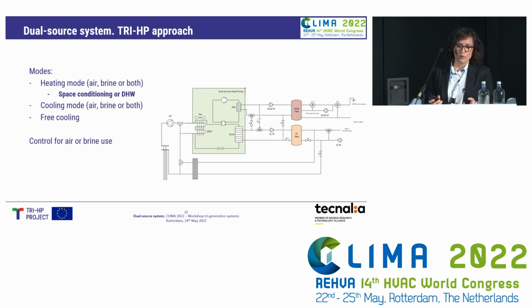Okay, this is an overview of the heat pump included in the building's thermal system. It can work in heating mode using air, the fan here, brine from the geothermal boreholes, or both at the same time, in order to provide space heating and domestic hot water. It's reversible, so it can also work in cooling mode, the same as in heating mode, with air, brine, or both at the same time. The system can also provide free cooling by exchanging heat directly with the boreholes. And the system is controlled for making a choice in using the air or brine, and also for the free cooling control.